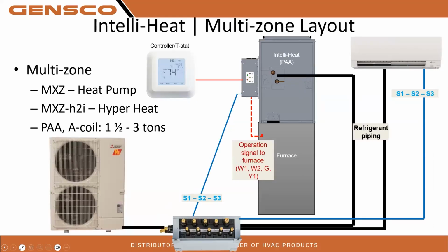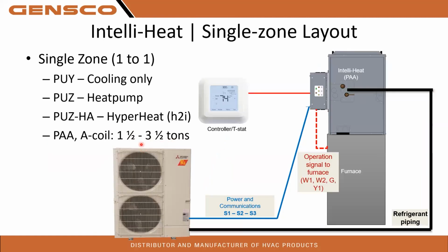These units can also be used on a multi-zone system. So MXZs, smart multi, and ported systems. We'll get a little bit more into compatibilities on that in a little bit. Here's an example on a branch box system. So you can see we have our MXZ heat pump with our branch box, going to 2 different indoor units. Standard wall mount here with our Intelli-Heat coil. Again, standard S1, S2, S3 wiring going to your coils there. One thing to note is on the ported systems or multi-zone systems, max is 3 ton. 1.5 to 3 ton, whereas on the one-to-ones, you can go to 3.5 ton.